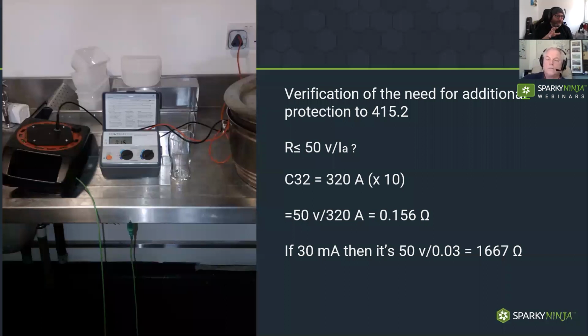You could be more accurate, to be fair, and measure a live to earth loop impedance - that would be more accurate because it could be more even. But yeah, you then just plug into Ohm's law and you're looking for 50 volts or less. If you have more than 50 volts, you need to either find a way to remove that, or if it can't be moved, it may need to be supplementary bonded.